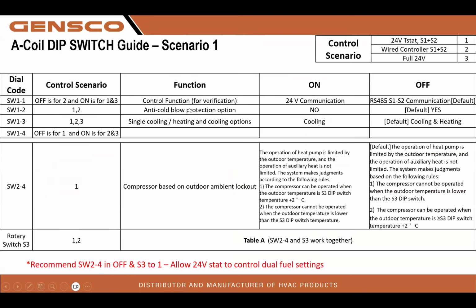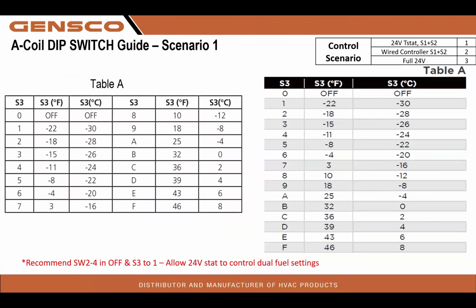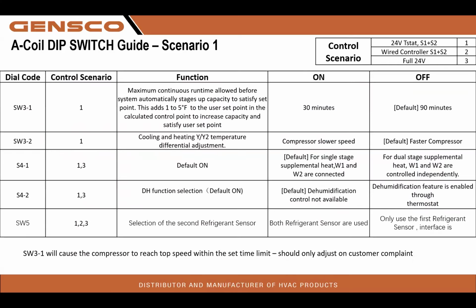Notice we were talking about the anti-cold blow option. When we go into defrost, we are not pumping this house full of cold air. Therefore, technically, we don't even need strip heat in the event you're going to be running an air handler. Control scenarios: if we want to lock out that outdoor unit based on a certain outdoor temp, we can do that and just run fossil fuel. Same dip switch settings we've already been talking about.